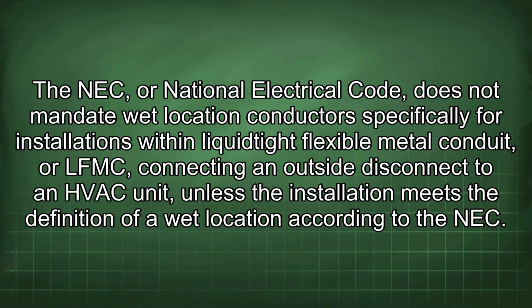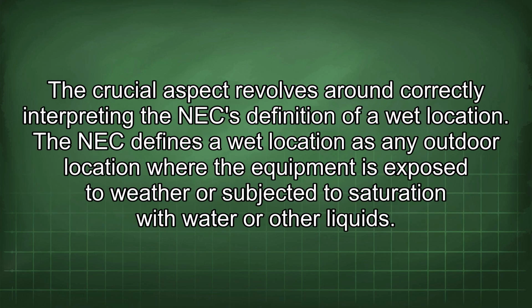The NEC, or National Electrical Code, does not mandate wet location conductors specifically for installations within Liquidtight Flexible Metal Conduit, or LFMC, connecting an outside disconnect to an HVAC unit unless the installation meets the definition of a wet location according to the NEC. The crucial aspect revolves around correctly interpreting the NEC definition of a wet location. The NEC defines a wet location as any outdoor location where the equipment is exposed to weather or subjected to saturation with water or other liquids.